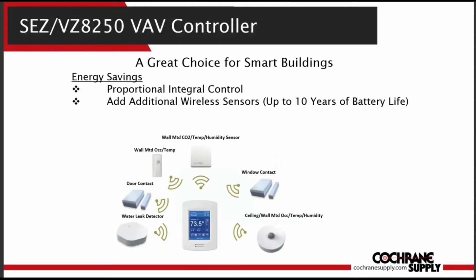Employing additional sensors can also help to save energy. As we saw in previous slides, sensors can be hardwired, but the 8250 room controllers can support up to 10 wireless sensors. Temperature and humidity sensors for remote sensing, averaging, high-low signal select, remote door or window contacts. If the window is open, disable the heating and cooling functions until the window is closed. Water leak detectors and occupancy sensors. The sensors can have up to 10 years of battery life and use standard off-the-shelf batteries.